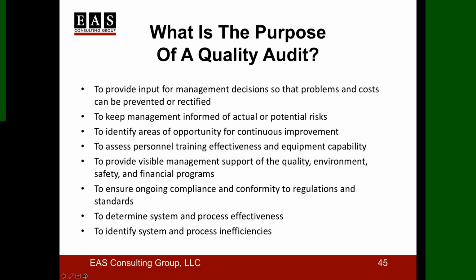And in medical devices, that includes the management representative. He or she is the liaison between quality and regulatory and top management. So they usually know if you do have a proper quality system or not. And they know from these quality audits whether we need to stop everything right now, or everything's fine and dandy. So that's the key of an audit. It's not just because FDA says so, it actually helps and improves quality systems.